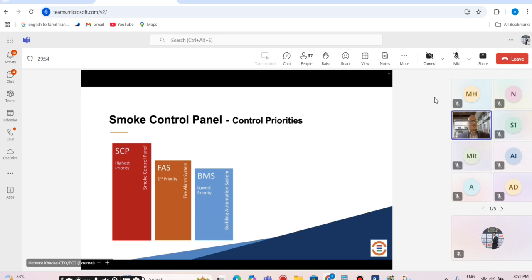So when you design a cause and effect matrix, especially the ICT people who are here in this room, they are instrumental in designing the cause and effect matrix. So that becomes the base for you to commission and operate your systems, all coordinated systems. NFPA 4 and 5 also addresses, NFPA 25 also addresses, especially NFPA 72, which is a fire alarm code, also addresses how your coordinated, integrated fire alarm systems are talking to all auxiliary systems when you design it, when you commission it.